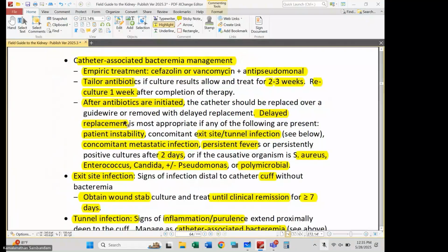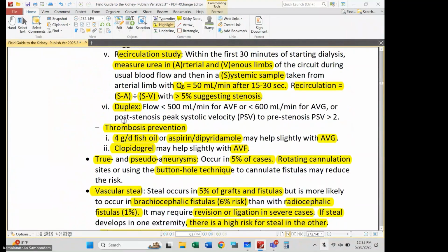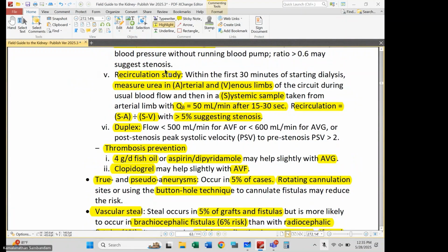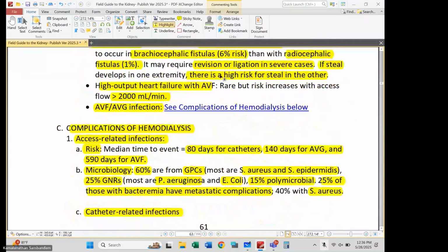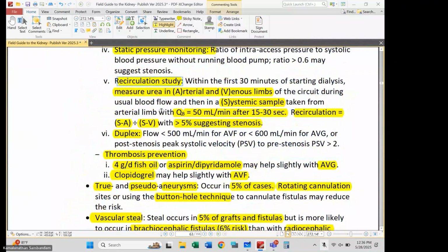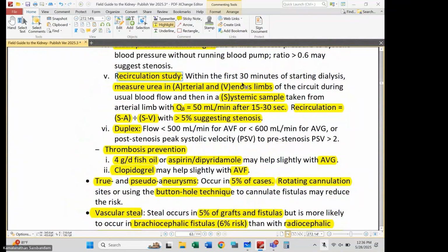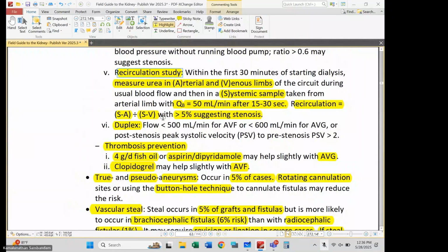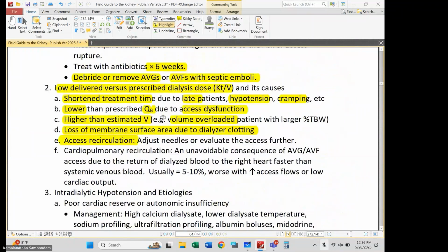Okay? Access recirculation. We talked about how you can measure access recirculation. There's a formula that I provided you up here. Remember, you can do an indirect test looking for access recirculation through those Transonic machines. Transonic machines are those often used machines for access surveillance. You typically get flow rates, and then they reverse the needles in order to measure a recirculation. And you can then do a formal recirculation study through this methodology that I described, transiently turning down the blood flow rate, measuring the so-called systemic, arterial, and venous concentrations of urea. Okay, so access recirculation will decrease KT over V.